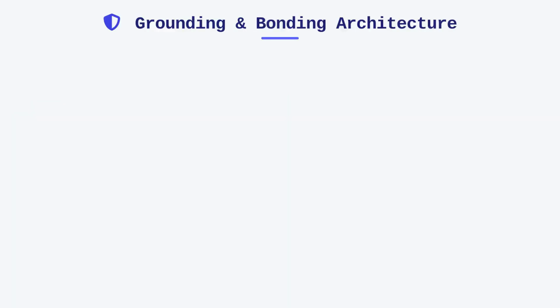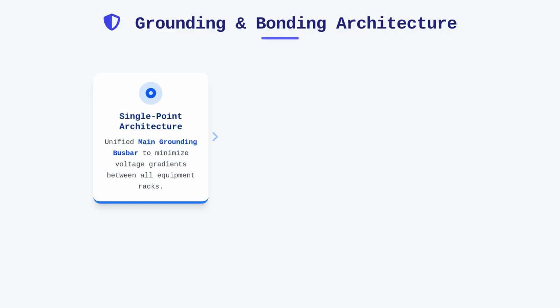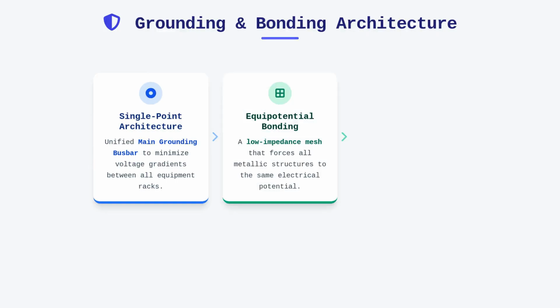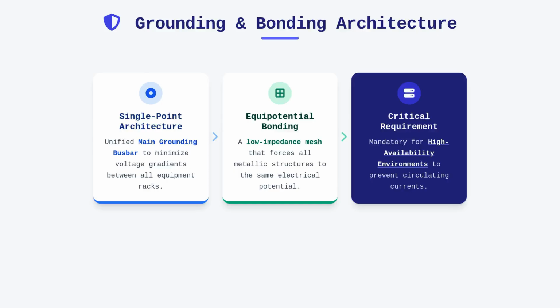The first line of defense against these circulating currents is the implementation of a coherent single-point grounding architecture. By ensuring that all equipment racks and cabinets ultimately reference a unified telecommunications main grounding busbar, we minimize the potential for voltage gradients between connected devices. This is further reinforced by the use of an equipotential bonding grid. Rather than relying on sporadic connections, a structured grid creates a low-impedance mesh that forces all metallic structures within the data space towards the same electrical potential. It is vital to understand that this is a strict requirement for high-availability environments.